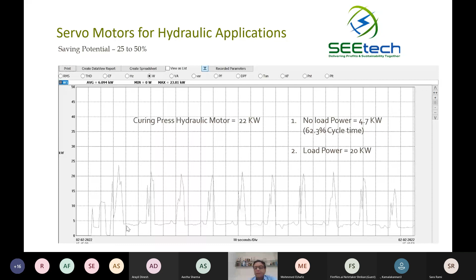So here, more than energy efficient motors, the focus is required on how to save on the no-load power. Many times in automation, what is done is that whenever it is on no-load, the RPM is reduced. But by doing that, the approaching or receding hammer speed goes down, and that is not liked by the process people. So what is the solution? The solution is a servo motor.